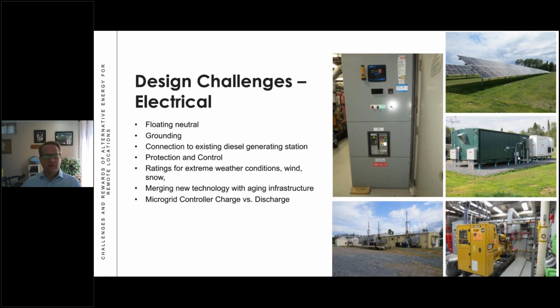In merging new technology with old technology, there were also some challenges within the microgrid controller itself too. With regards to harmonic distortion, when we analyzed the microgrid operating under several different conditions, we observed that the second harmonic distortion was affecting the charging rate of the batteries. So we had to reduce the charging speed of those batteries to bring the distortion down to acceptable levels, and that resolved the issue.